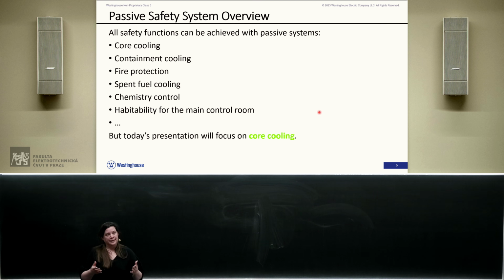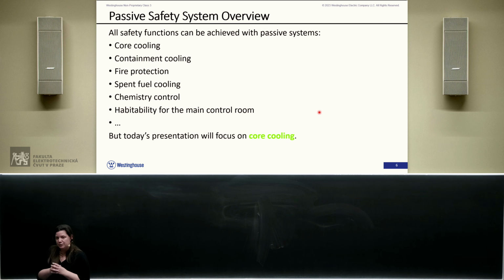That is done by having a system that can still take the heat away from the core and put it somewhere else. We don't want to leave it in the reactor coolant system because we also want to protect that system, so we need to transfer it somewhere - that somewhere is going to be the containment atmosphere, as we're going to see. And we also need to take it away from the containment because we want to protect the containment from overheating. Fire protection, as the name indicates, well as anywhere, a fire could one day happen, and we need to be sure our plant is safe in case of a fire.